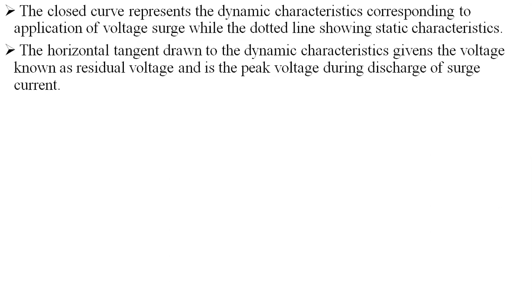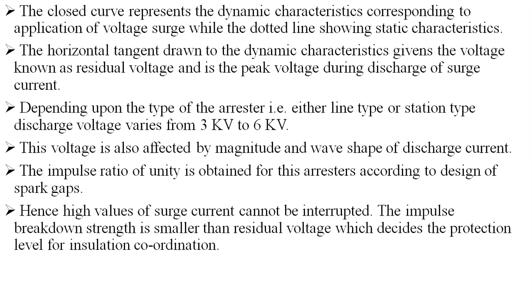Depending upon the type of arrestor, that is either line type or station type, discharge voltage varies from 3 kV to 6 kV. This voltage is also affected by the magnitude and wave shape of the discharging current. An impulse ratio of unity is obtained for these arrestors according to the design of the spark gaps. Hence, high values of surge current cannot be interrupted. The impulse breakdown strength is smaller than the residual voltage, which decides the protection level for insulation coordination.